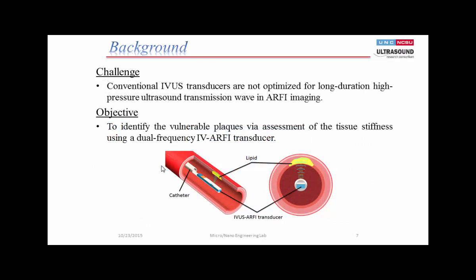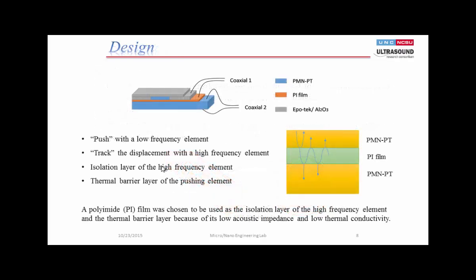Conventional IVUS uses arrays at about 20 MHz, or single elements at 40, 45, 50, up to 60 MHz. That high frequency might not be very efficient for ARFI, which requires pushing and tracking. So we look at those requirements to determine what kind of IVUS transducer we can make. Similar to Dr. Ma's presentation, we want a dual-frequency design: low frequency as a pushing transducer, and high frequency at the front as the tracking transducer. This is similar to our acoustic angiography or superharmonic imaging design, with a high-frequency tracking layer, an isolation layer in between, and the low-frequency pushing transducer at the bottom.